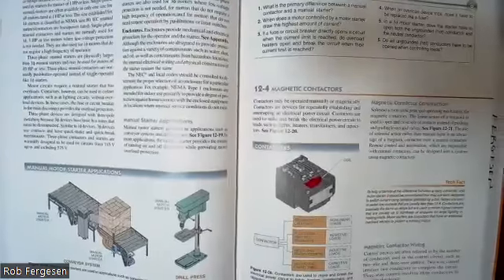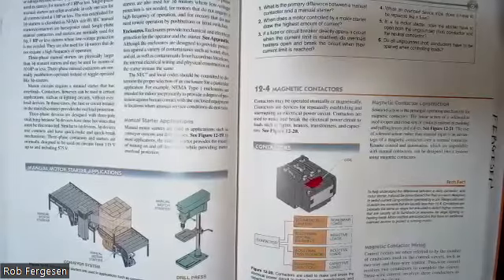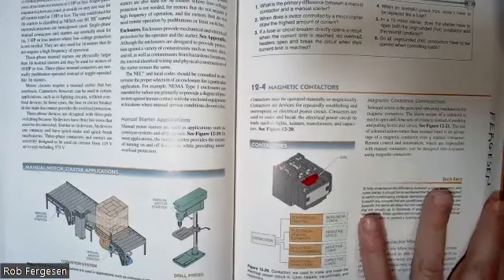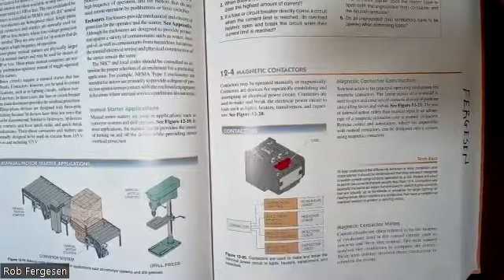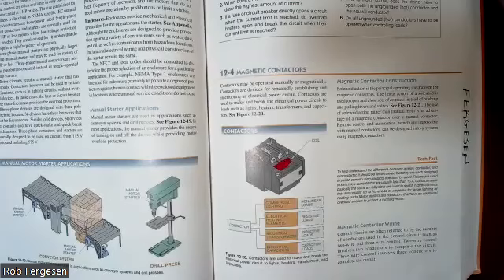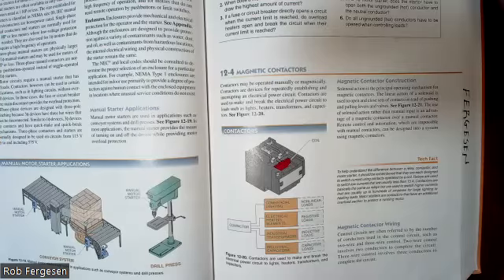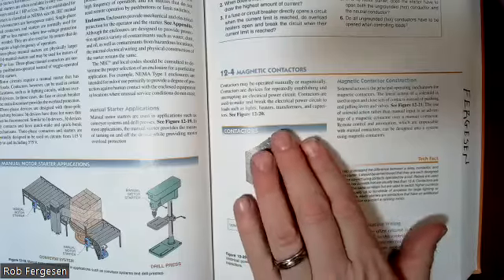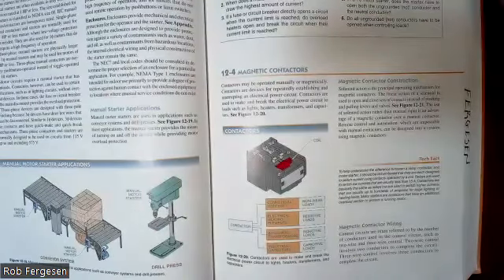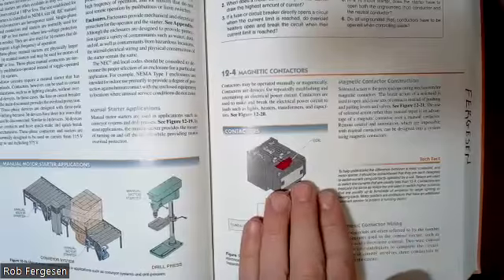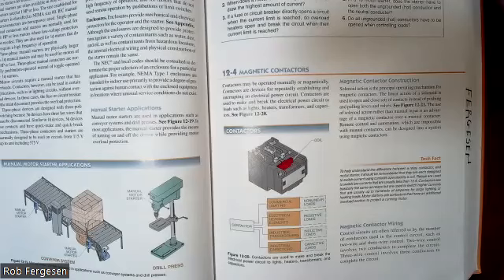So we're on page 247. We're now talking about magnetic contactors. So contactor is just basically saying it's a big switch, and a magnetic contactor implies that we have an electromagnet. If you use a small amount of current and a smaller voltage, you can control a switch that will control a lot higher voltage and current. And that is why we have a control voltage. We want to have a control voltage through smaller push buttons and smaller switches that can turn on and off a big motor out there. And so that's what a contactor is for. It allows me to turn on and off with a small voltage using a coil and a small electromagnet. It'll turn on and off a big voltage.